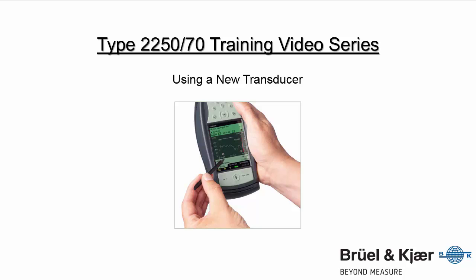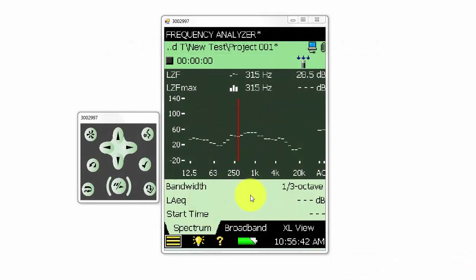In this training video, we will review how to create a new transducer in a 2250 or 2270 sound level meter. The process is the same for all templates on the sound level meter.